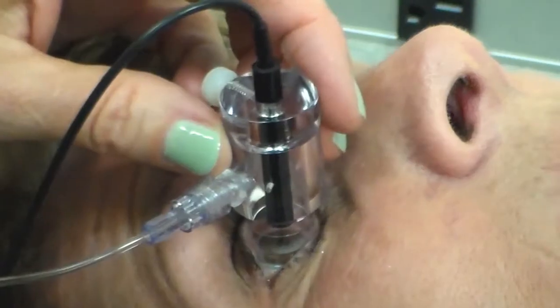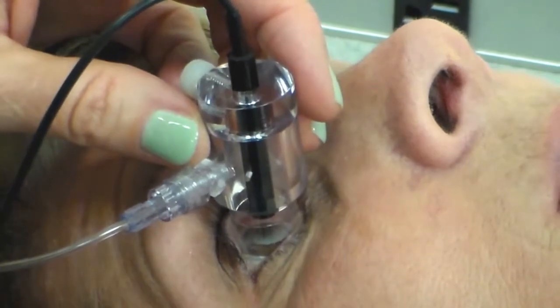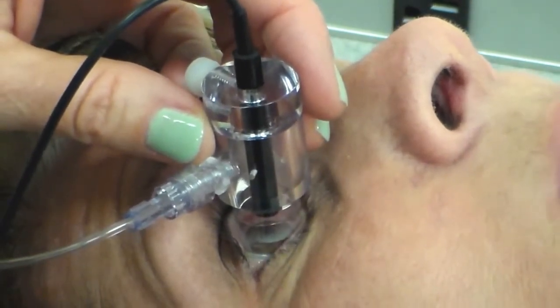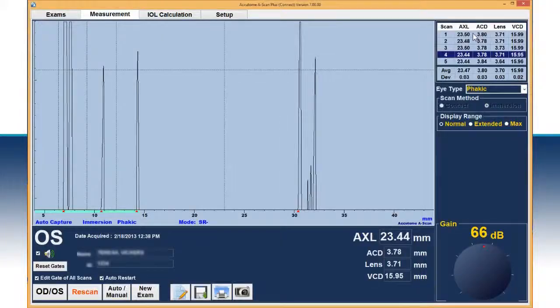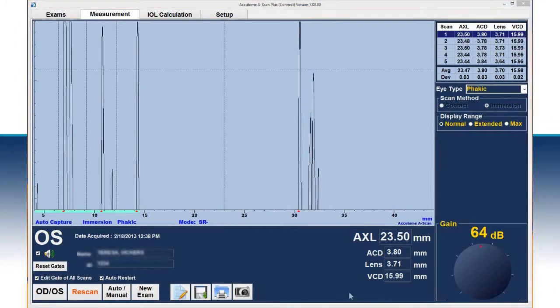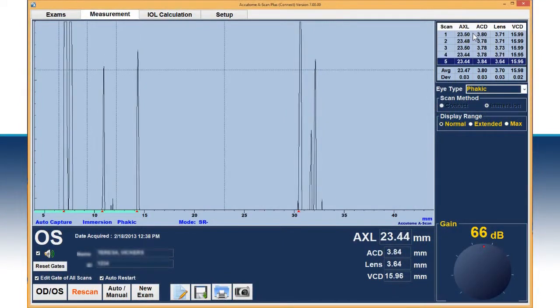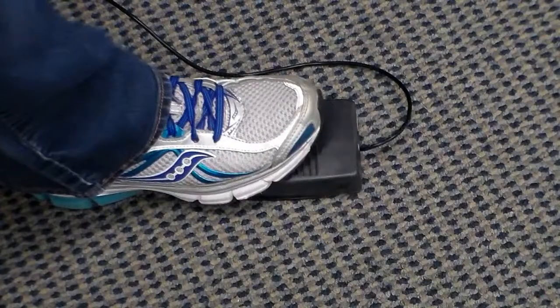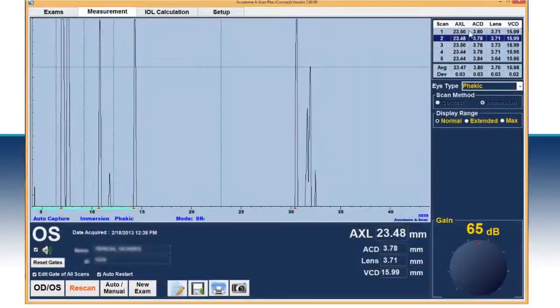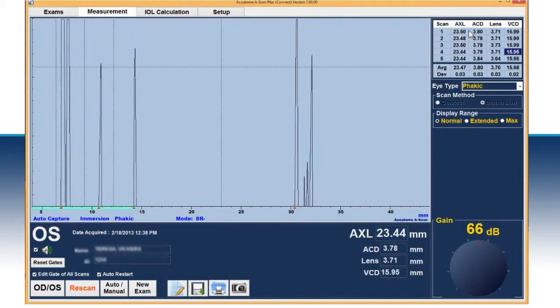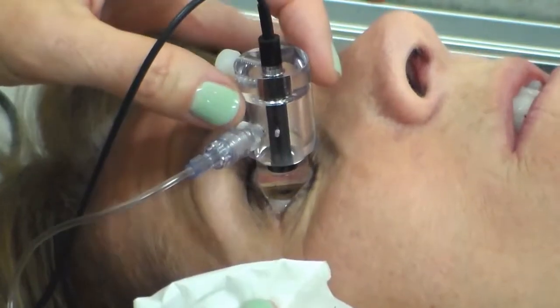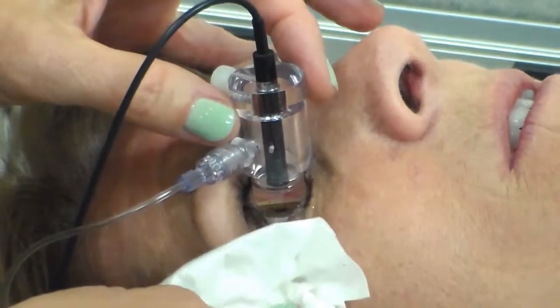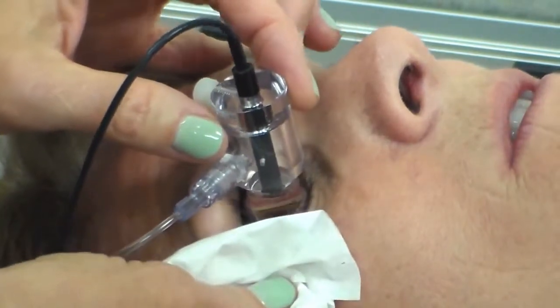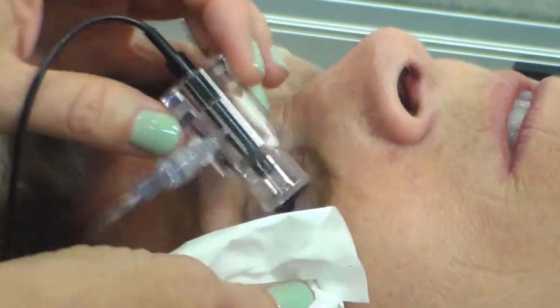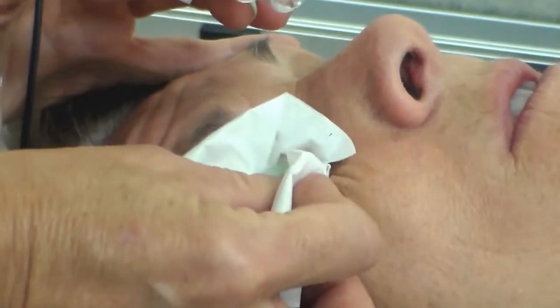If needed, adjust the shell slightly to properly align the sound beam along the visual axis in order to achieve the proper waveform pattern. The A-Scan will rapidly capture 5 axial length measurements. Gently tap the foot pedal to review the scans. Once all scans have been reviewed and deemed acceptable, gently remove the shell from the patient's eye by tilting the shell toward the nose bridge and capturing the water in a tissue.